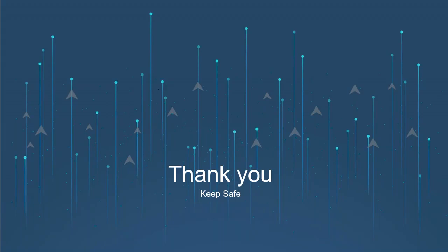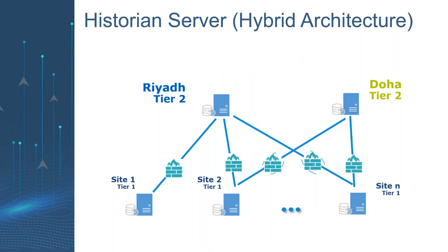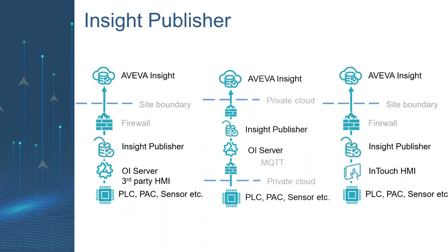Next one: can the M262 or any other PLC that can publish MQTT be connected to AVEVA Insight? And can it be done directly, or do we need a broker first? Yes, exactly. This is what I showed, thank you for this question. Let me go back to the Insight Publisher. In case you have MQTT, no, it's not directly from a broker to Insight. You have to take it to your OI server and send it to AVEVA Insight. And this will be done with AVEVA Publisher, when you import the Excel sheet.